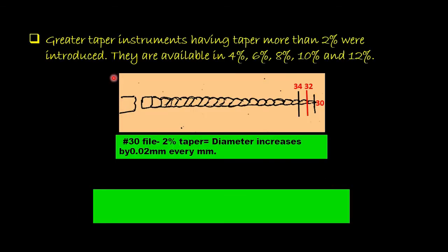Greater taper instruments that have a taper more than 2% were introduced, and they are available in 4%, 6%, 8%, 10%, and 12%. If we have a file that has a taper of about 2%, it means diameter increases by 0.02 mm per millimeter.